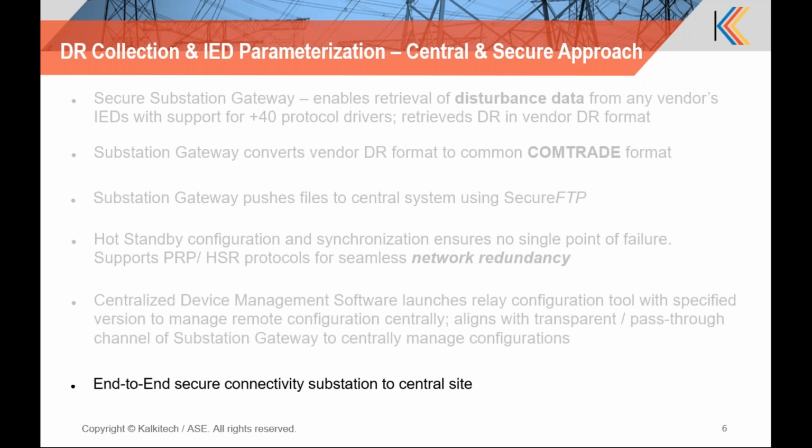Then end-to-end security is ensured. The substation to center link is through a TLS 1.2 tunnel, and we also have role-based access control. If live data transfer is needed, we support 62351-based DNP3 secure authentication. So all those secure mechanisms are needed to support the complete connectivity, and for system-level security as per the NERC 5.0 standards, we support that on the complete system.